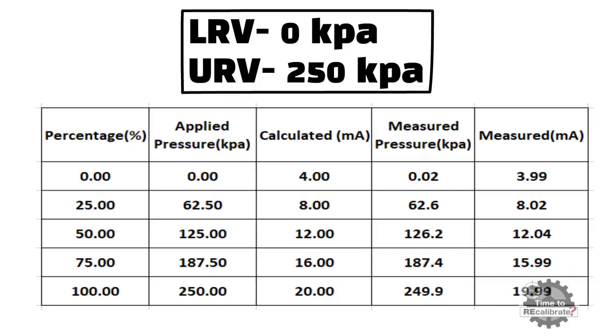Put the 4 to 20 mA analog output standard values in the calculated milliampere column. For example, when there is 0% input, calculated analog output value is 4 mA. Write down this value in the calculated milliampere column. When there is 25% input, standard analog output value is 8 milliampere. And when there is 50% input, standard analog output value is 12 milliampere. Standard analog output value is 16 milliampere for 75% of input. And standard analog output value is 20 milliampere for 100% of input.